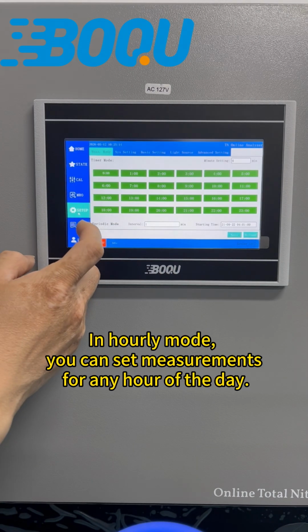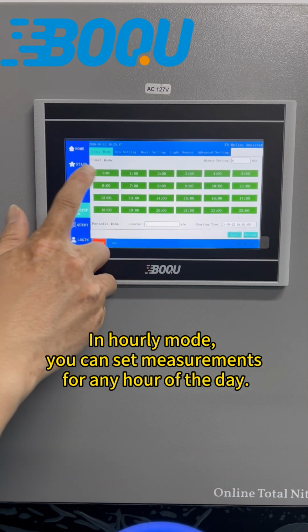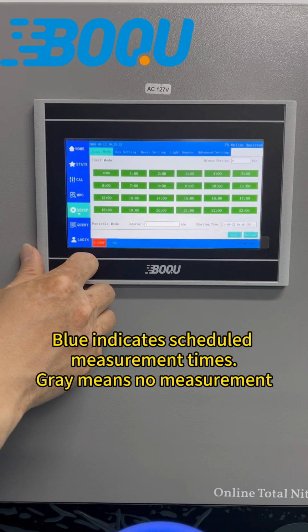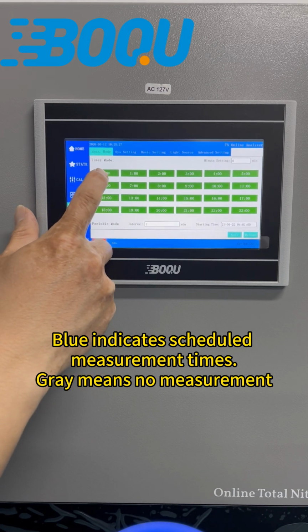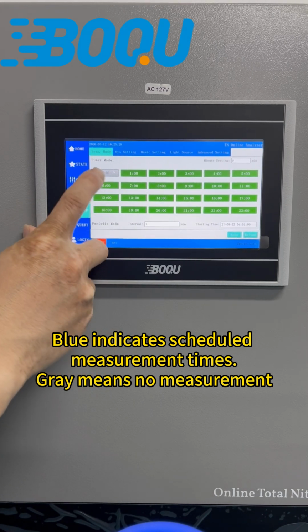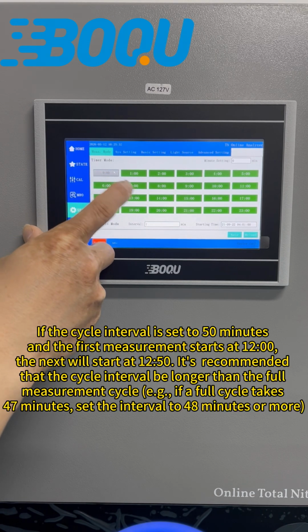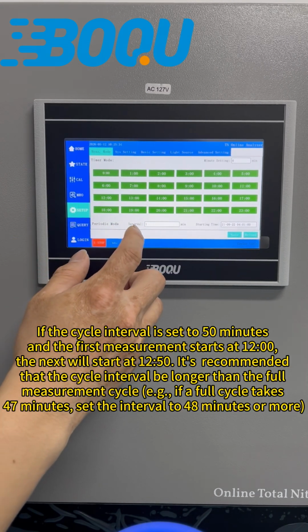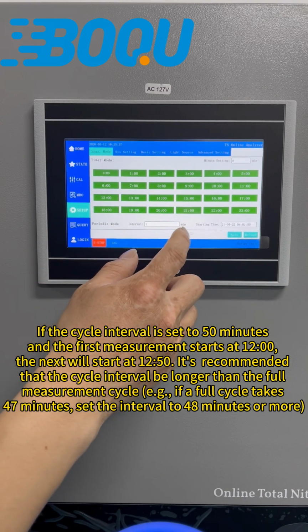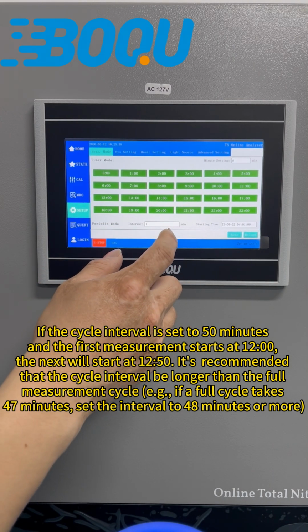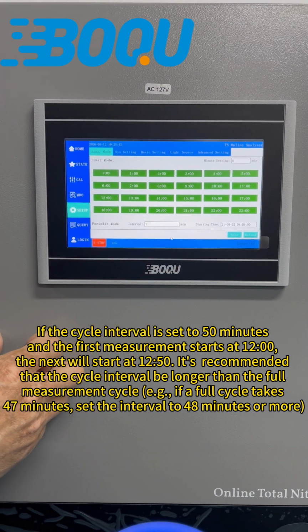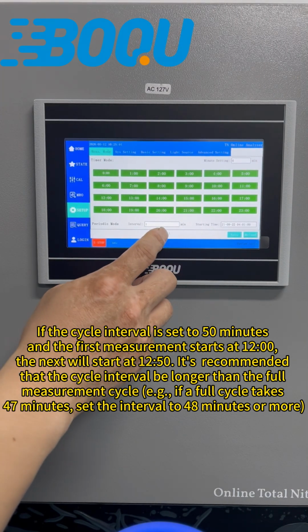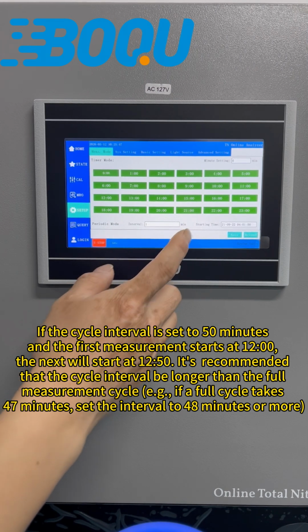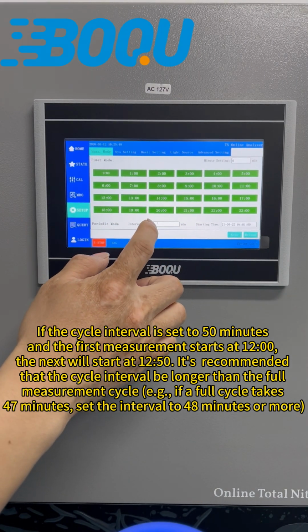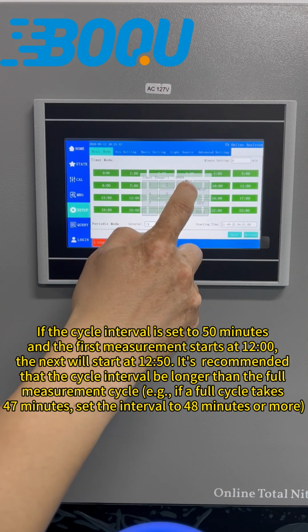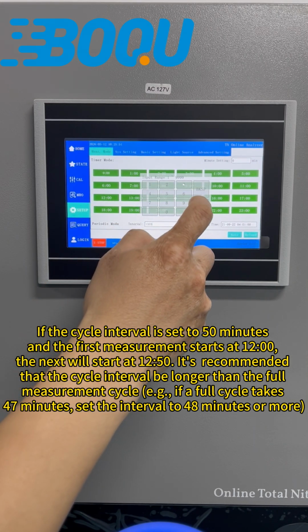In hourly mode, you can set measurements for any hour of the day. Blue indicates scheduled measurement times. Gray means no measurement. If the cycle interval is set to 50 minutes, and the first measurement starts at 12 o'clock, the next will start at 12:50. It's recommended that the cycle interval be longer than the full measurement cycle. If a full cycle takes 47 minutes, set the interval to 48 minutes or more.